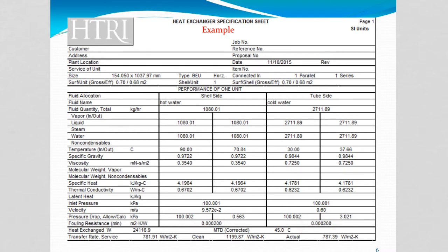aspect here, where heat exchangers are not used in a perfect world. If you, for example, take a seawater to freshwater heat exchanger, it's going to get dirty quite quickly, and it needs, by the way, to be periodically cleaned. So you need to build in some factor in your heat exchanger so it doesn't reflect an ideal situation, but an average, realistic working operation.